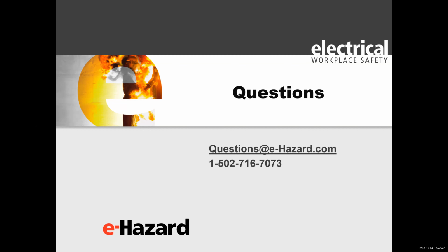Next question, Hugh: what type of testing is done on voltage gloves as far as melting rubber? Well, if they have an arc rating, we have a standard for arc rating rubber insulating gloves, but there's no requirement in the standard to do that. As we've had a proliferation of brands of gloves, I do think there's concern on some people's parts. As long as you're not over about 15, 20 calories exposure, the gloves I've tested are usually not a hazard unless they're very, very thin gloves. But you want to talk with your glove manufacturer and see if they have an arc rating, because they will have an arc rating and an ignition withstand.